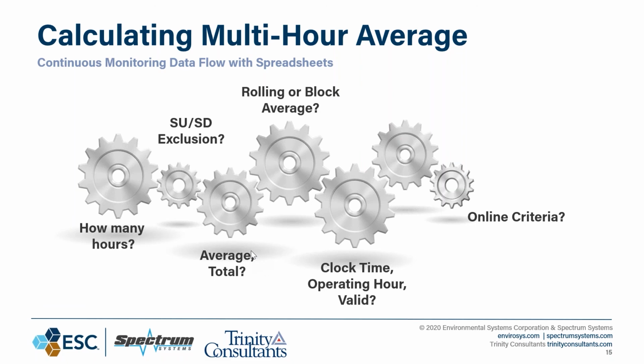Because this piece is important for preventing the next exceedance. If you know where you're at in the hour, or if you're in a 3-hour rolling average, you can back off the units and give yourself enough time to prevent an exceedance. If the operators understand that, and the control room operators are trained on the permits, and they have an easy cheat sheet for calculating your averages, it'll be a lot easier for them to respond in the event of an excursion or an exceedance for NOx, CO, or any of the things that are monitored. Right, you don't have to be smarter than the DAS, you just need to have a reasonable idea of what to expect from it.